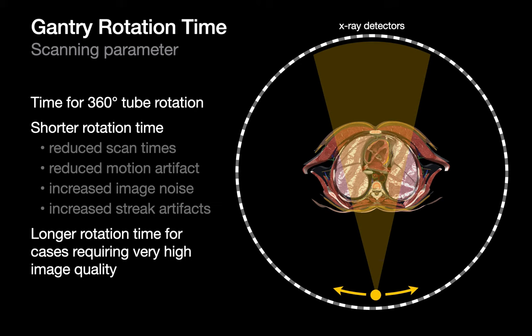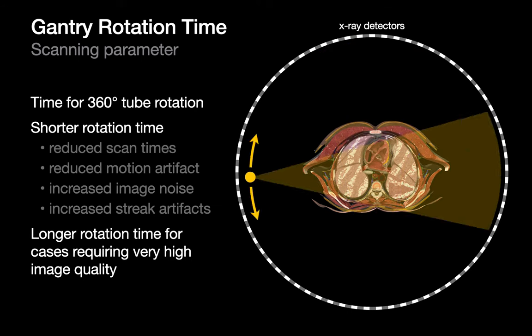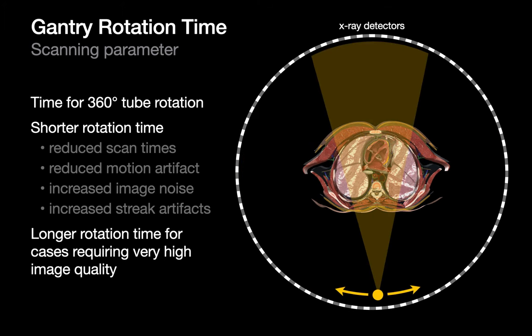Gantry rotation time is the amount of time it takes for the x-ray tube to revolve once around the patient. Shorter gantry rotation time means the tube completes one revolution faster, reducing scan times and motion artifact, but at the cost of more image noise and streak artifacts. As long as the body part is relatively fixed, slower tube rotation — longer gantry rotation time — results in better image quality, important for fine structures like the inner ear and temporal bone.